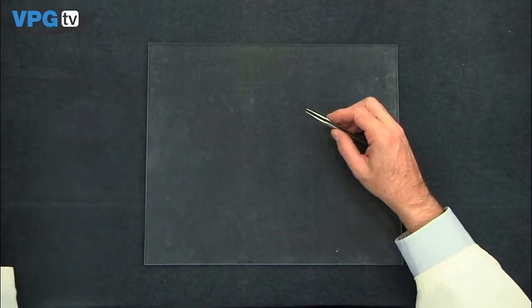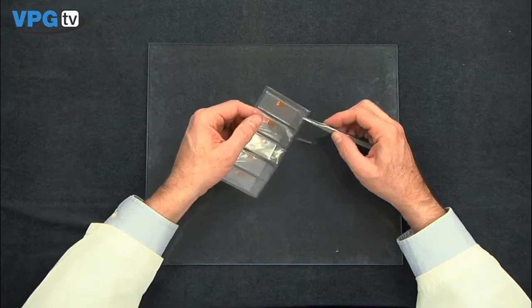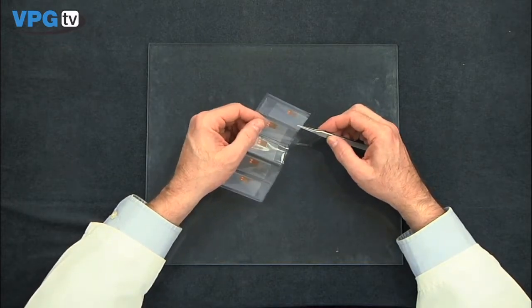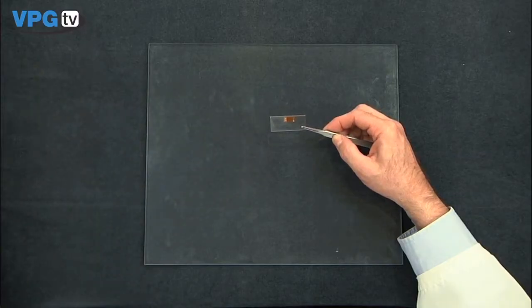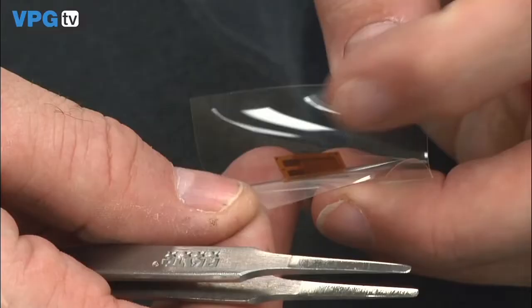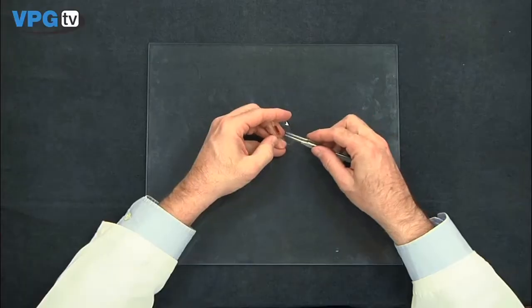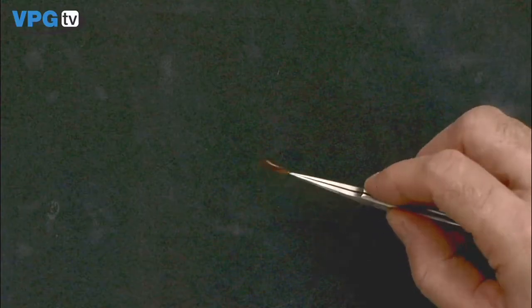We are using a CEA series strain gauge, which has polyimide backing, an encapsulating layer, and large copper-coated tabs. Carefully remove the Mylar folder containing the gauge from the plastic pouch. Hold the Mylar folder open in a butterfly fashion. Grasp the gauge carefully at one corner near the tabs, without touching the grid area.